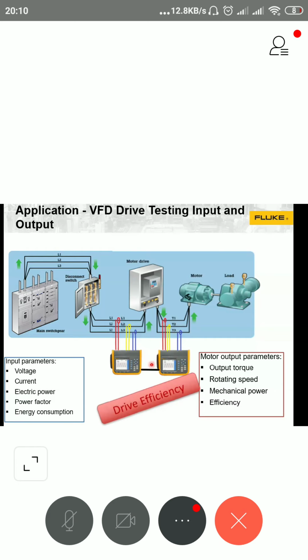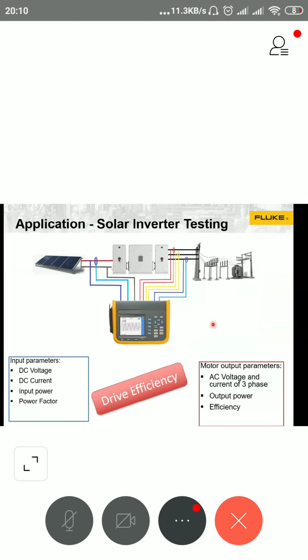And since this equipment has optional torque and speed interfaces available, for an end user it is very useful. Without any hurdles, you can connect a torque and a speed sensor and also measure the torque and the speed on the motor side. And similarly, when it comes to solar inverter testing, checking the inverter efficiency is one of the major parameters. Because earlier we used to connect a power analyzer here and another power analyzer here, start the measurement at the same time, end the measurement at the same time, and manually calculate.